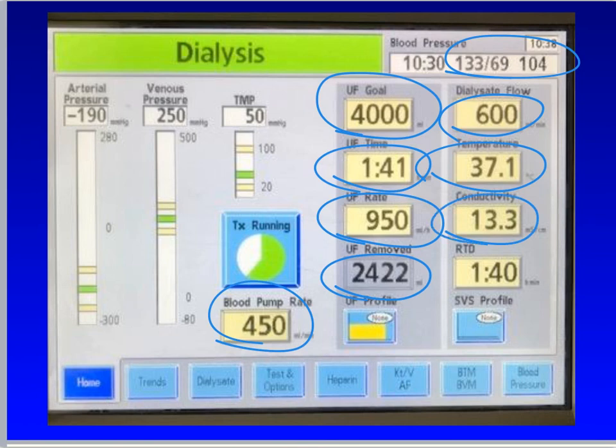within the blood lines that are leaving the patient, negative because the roller pump is pulling blood out, and returning to the patient, positive because the blood is being pushed back into the patient's vein. Note that with both dialysis and CVVH, when a dual lumen dialysis catheter is used for access, the exiting and entering blood lines are actually both venous blood. They are labeled arterial and venous only so that we can keep track of which one is leaving the patient and which is entering.